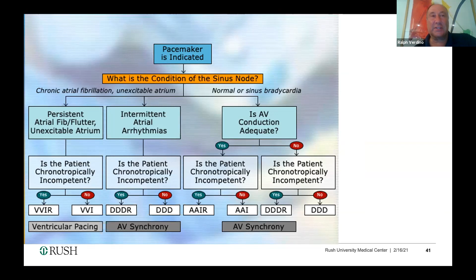You're right that it's the vulnerable period, but remember, before we had these very sophisticated devices that we can check over the telephone, we used to do telephone checks of pacemakers where the person put the magnet on and we were able to see how much battery is in there, because pacemakers pace at a specific rate depending upon their model for how much battery is left in the device. So that was our way. Now, you get it remotely and it's very easy.